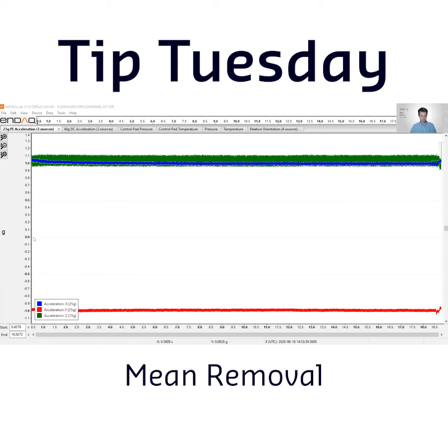here. Piezoelectric accelerometers have a DC bias that can shift your data as the temperature changes, and that's bad. You don't want that. But it's hard to account for with the calibration that we do, so we allow our software to correct for it in post-processing.